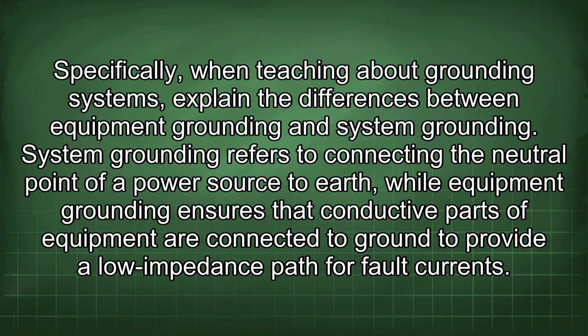Specifically, when teaching about grounding systems, explain the differences between equipment grounding and system grounding. System grounding refers to connecting the neutral point of a power source to earth, while equipment grounding ensures that conductive parts of equipment are connected to ground to provide a low impedance path for fault currents.